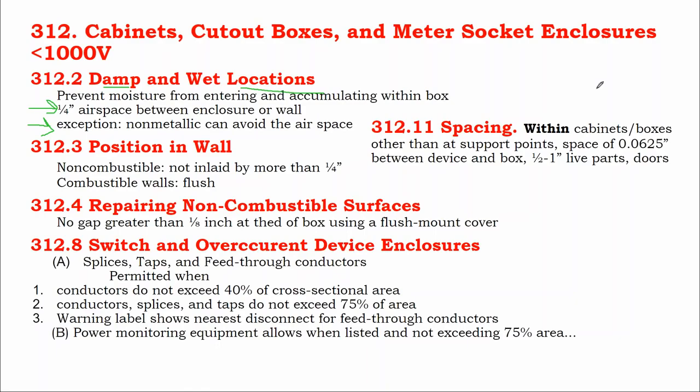But if you just bought a generic metal box and screwed it directly to a concrete asphalt wall, that could be a code violation. The temperature differential between the wall and the hotter inside of the box could cause moisture to accumulate, which you don't want around electrical terminals. But it says, well, if it's plastic, that's fine. Plastic, better insulation, you don't have that issue.